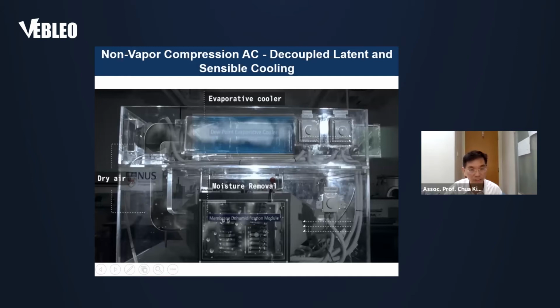Then it goes through the second stage, the dew point evaporative cooler, where 15% of the air goes through the wet channel to cool the air in the dry channel. So the air exiting the dew point evaporative cooler is both cool and dry, the exit point of this new generation air conditioner.